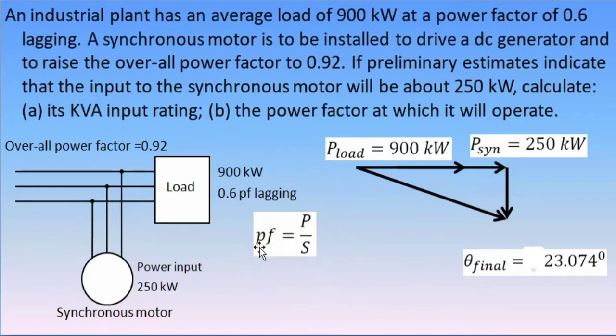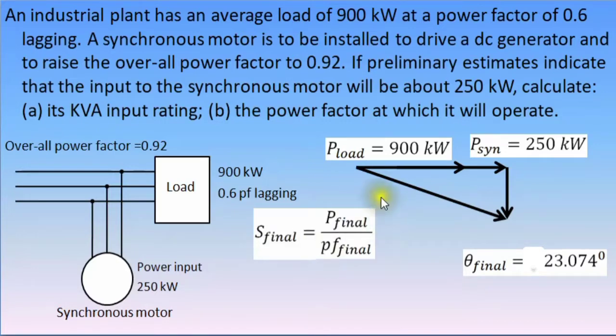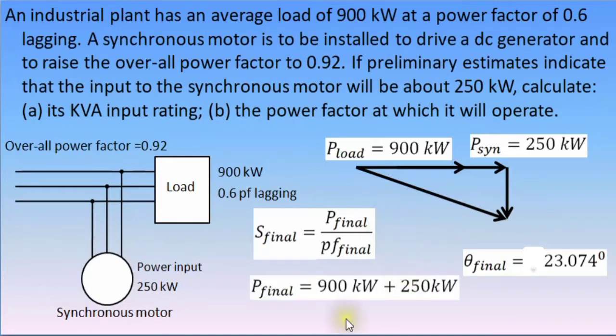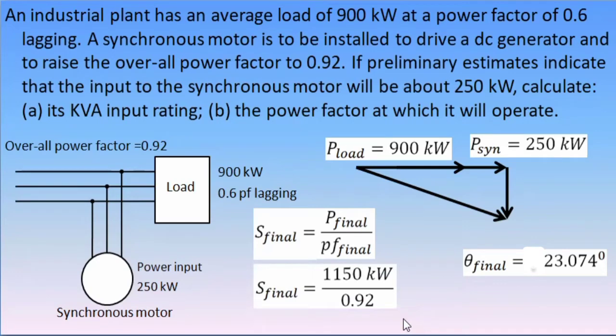Again, we could use this formula to determine the apparent power. Cross-multiply the power factor and the apparent power. We have the apparent power equals the real power or the effective power divided by the power factor. And the total or final effective power of the system is 900 kilowatts plus 250 kilowatts. This is 1,150 kilowatts. Substituting this value to determine its apparent power, we have 1,150 kilowatts divided by 0.92. The answer is 1,250 kVA.